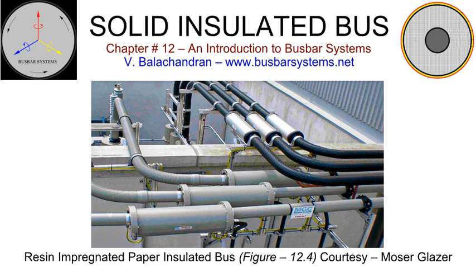Cast resin insulators, bushings, and instrument transformers for medium voltage applications have been in operation for many decades. The casting process of the components is well understood. However, when the paper is impregnated with resin, as in the case of a solid insulated bus, the resin undergoes a chemical transformation. The entrapment of moisture or air will adversely affect the dielectric properties of the product. Reprocessing cannot be carried out to rectify defects. The process of impregnating paper with resin was developed by Moser Glaser in the late 1950s. The process was subsequently adopted, modified, and improved with the development of new resin formulations.